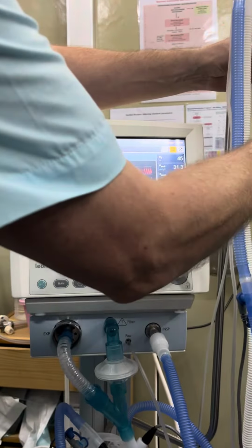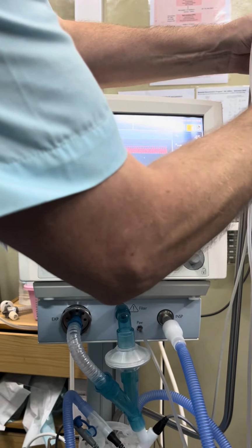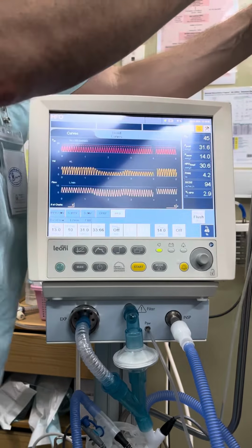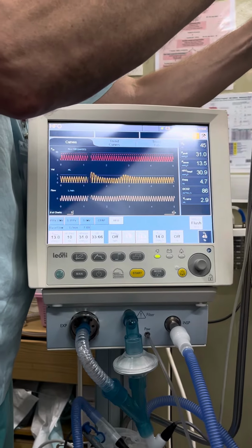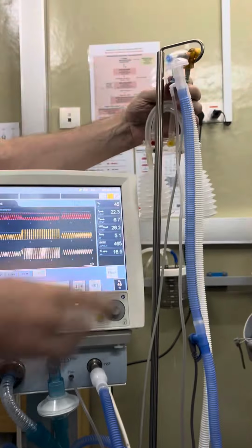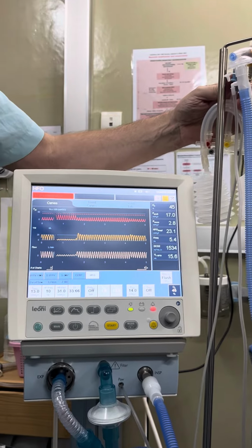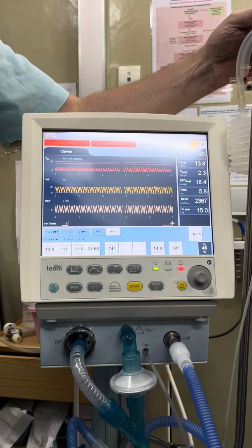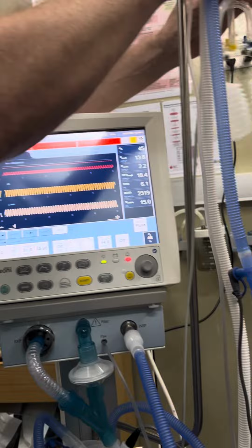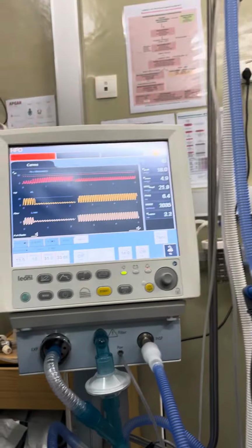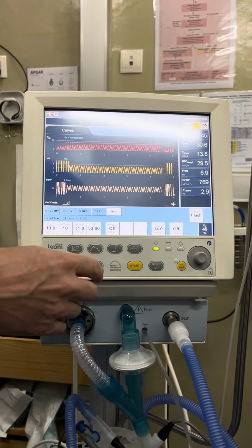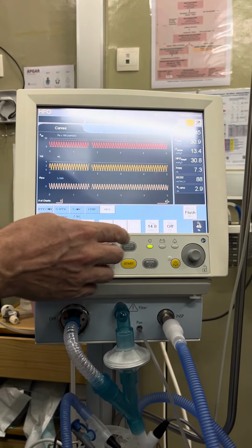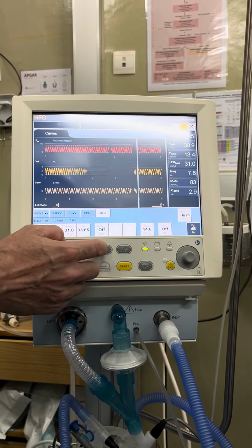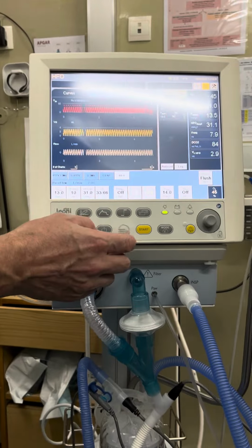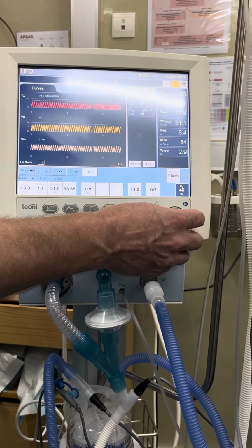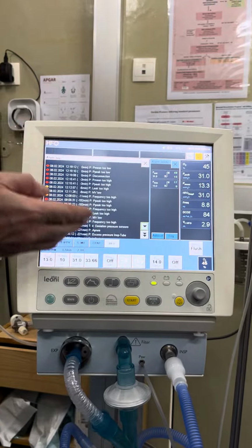Still not alarming. Still not alarming. Let's see what happens if I take it off. So, disconnection. Okay. The machine didn't like that. That's good. So we need to reconnect and check the alarm history if we want to. So here, in the log, you can see all the alarms that have been.